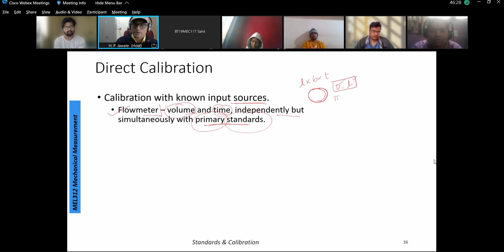Calibrated device can act as a secondary standard. If the device, for example a flow meter, is calibrated, that accuracy is established, that our flow meter is accurate to all the measurement up to say 0.1% of the given measurement. Then once it is clearly identified, this device can be used as a calibration instrument for other flow meters which are a little less accurate than the given calibrated flow meter. Thus, it shows that once a flow meter is calibrated, it can be used as a secondary standard for calibration of other flow meters which are a little less accurate than the one being calibrated.